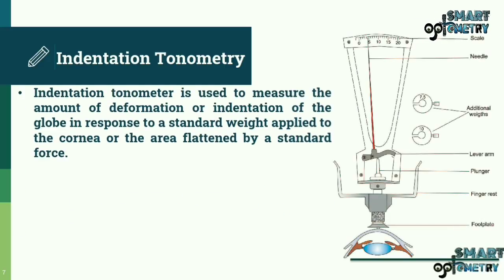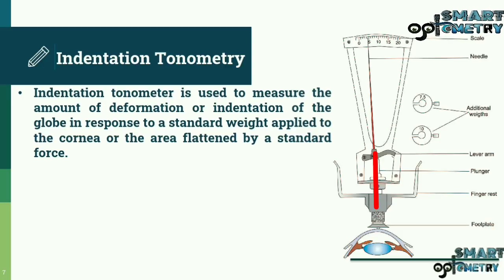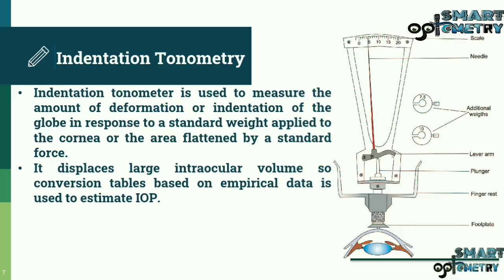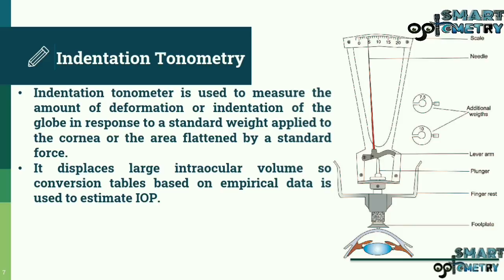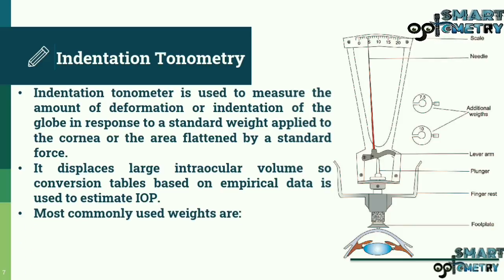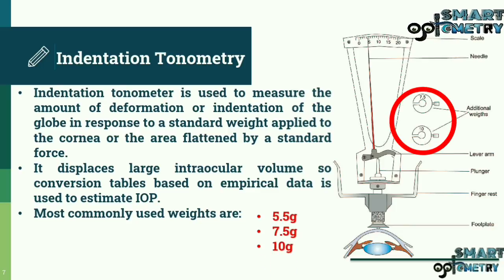Indentation Tonometry measures the amount of deformation or indentation of the globe in response to a standard weight applied to the cornea, or the area flattened by a standard force. It displaces a large intraocular volume, so a conversion table based on empirical data is used to estimate IOP. The most commonly used weights are 5.5 g, 7.5 g, and 10 g.